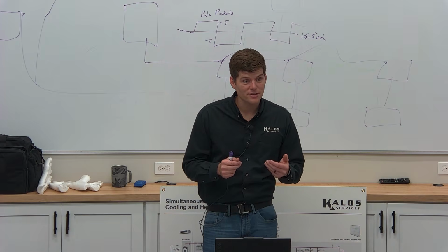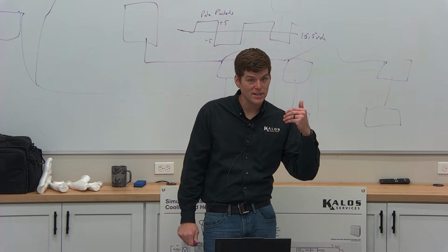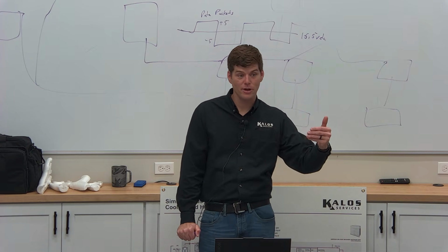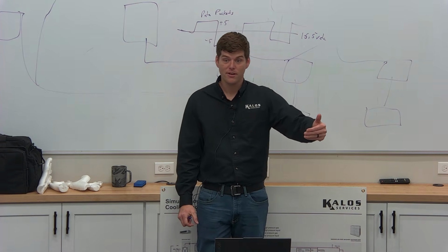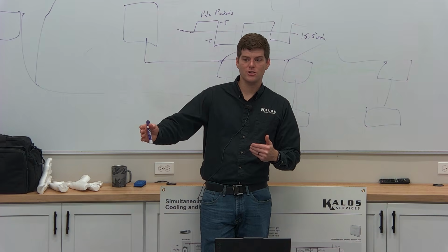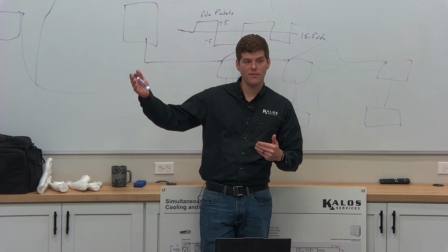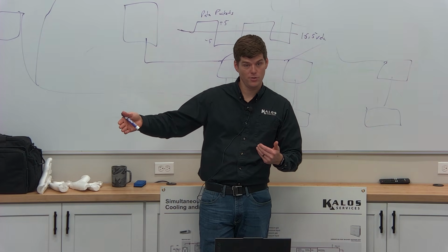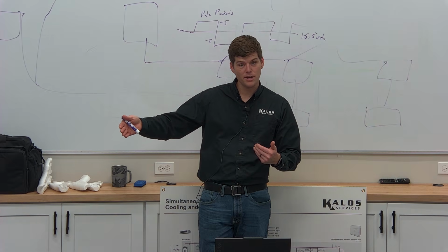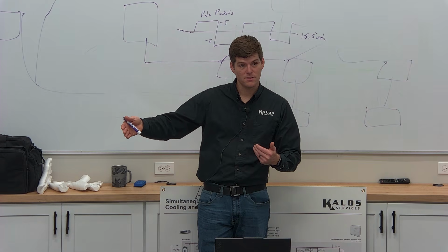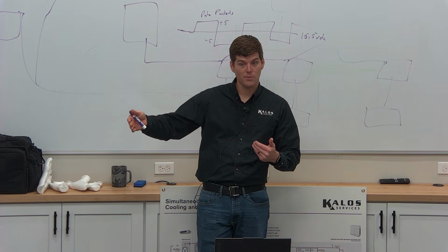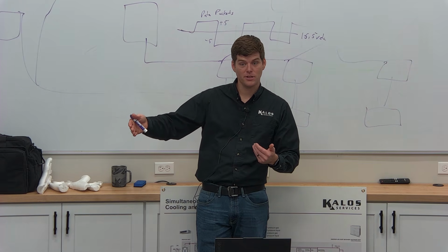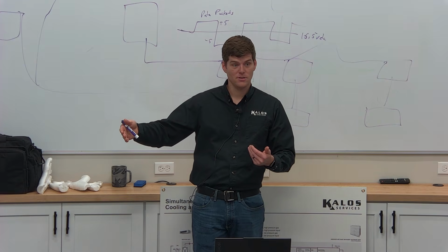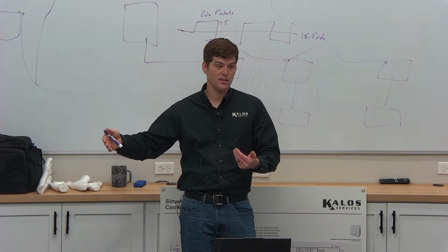Based upon temperature sensors. If I have refrigerant leaving my expansion valve at a low pressure saturated vapor, it goes through my heat exchanger and exchanges heat and comes out the other side, and I have a 20-degree superheat. My indoor unit then says 20-degree superheat. No, I'm looking for a 9. Open up expansion valve, 25 pulses. Superheat doesn't change. Open up valve, 25 pulses. Superheat doesn't change. Open up 50 pulses. Superheat goes down by 1 degree, it's 19 degrees.